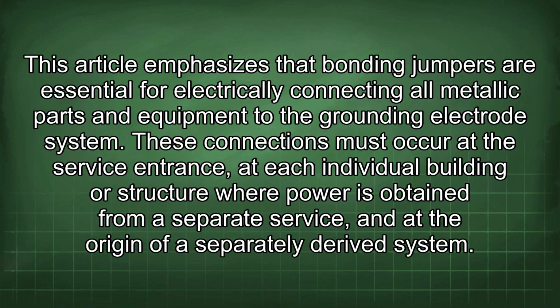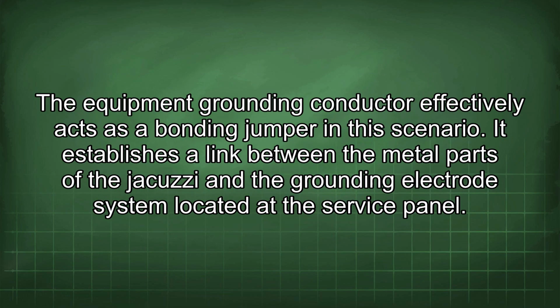This article emphasizes that bonding jumpers are essential for electrically connecting all metallic parts and equipment to the grounding electrode system. These connections must occur at the service entrance, at each individual building or structure where power is obtained from a separate service, and at the origin of a separately derived system. The equipment grounding conductor effectively acts as a bonding jumper in this scenario.